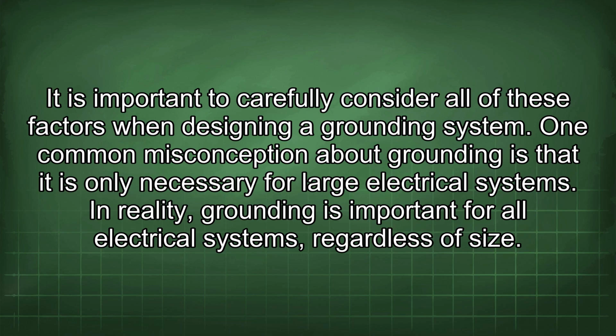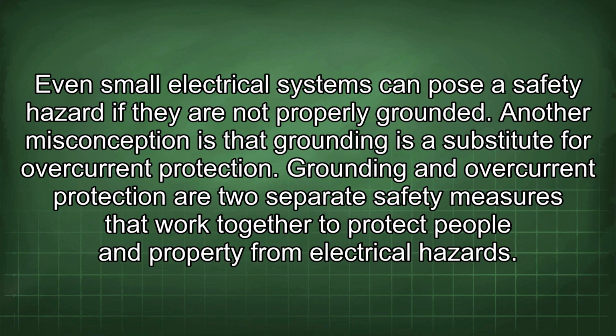One common misconception about grounding is that it is only necessary for large electrical systems. In reality, grounding is important for all electrical systems, regardless of size. Even small electrical systems can pose a safety hazard if they are not properly grounded. Another misconception is that grounding is a substitute for overcurrent protection. Grounding and overcurrent protection are two separate safety measures that work together to protect people and property from electrical hazards.